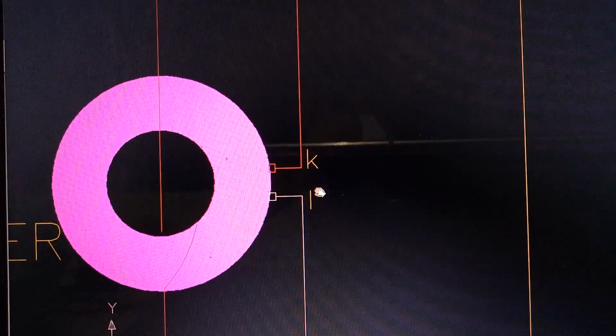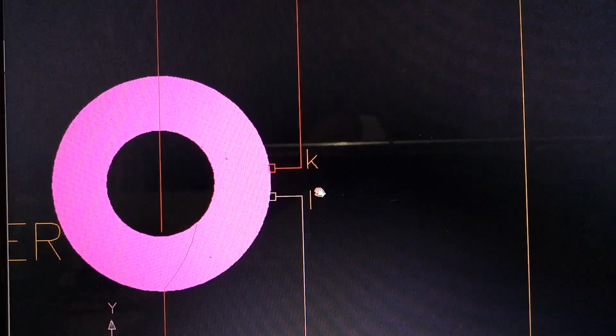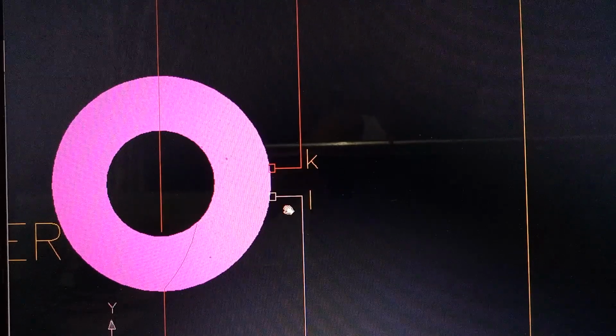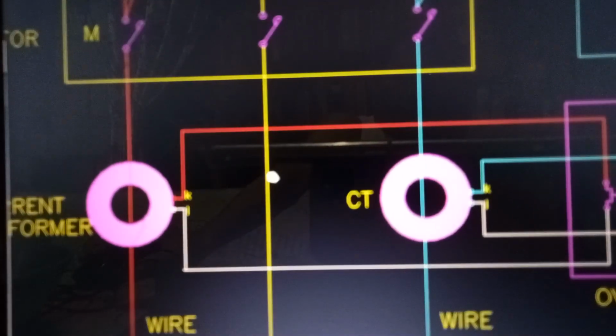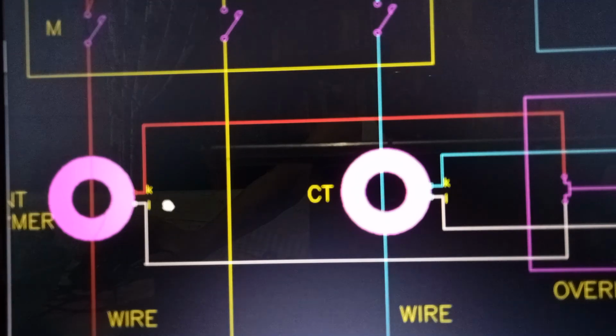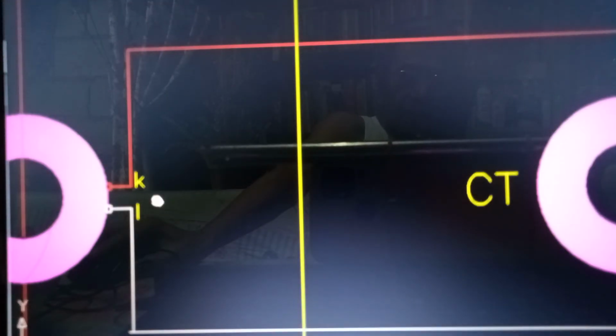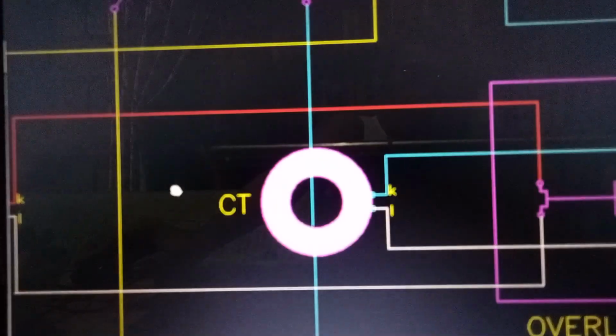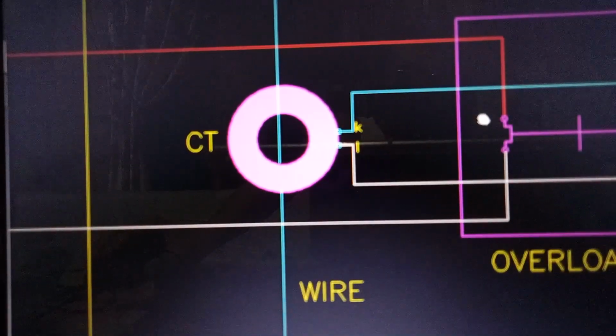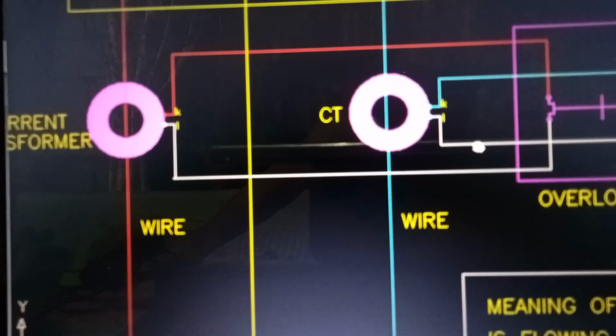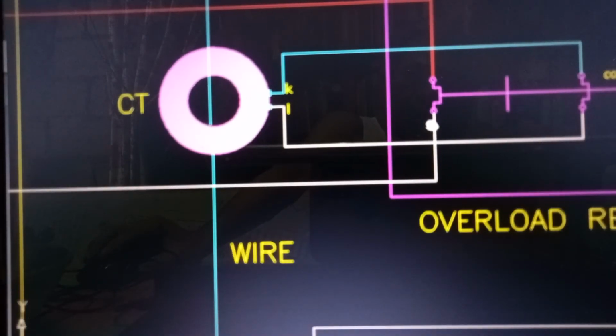The secondary terminals of the current transformer are labeled as small letter K and small letter L. This is a Japanese made current transformer. If we are going to use a US made current transformer, this will be X1 and the other terminal will be X2. So here we can see that the secondary terminal letter K on the CT connected to line 1 is now connected to the heater of the overload relay for line 1. And the secondary terminal small letter L is connected on the load side of the heater on line 1.